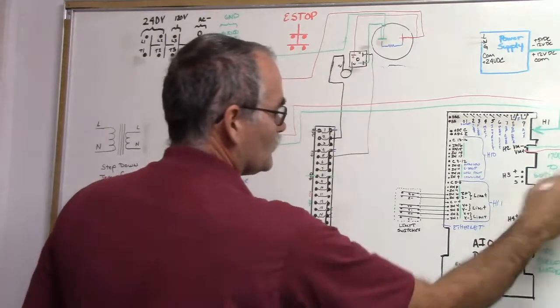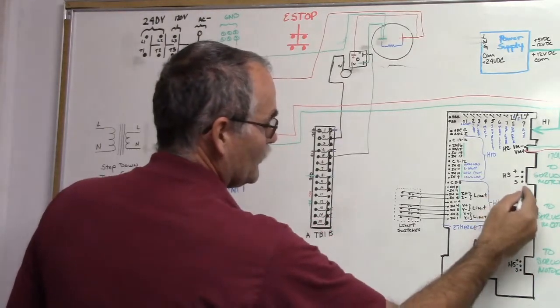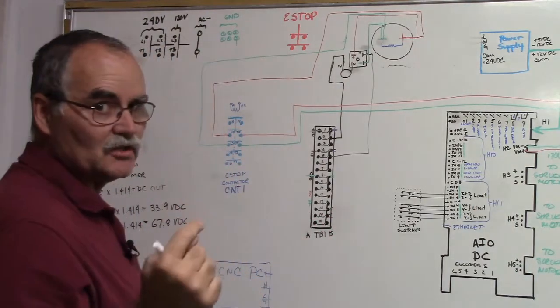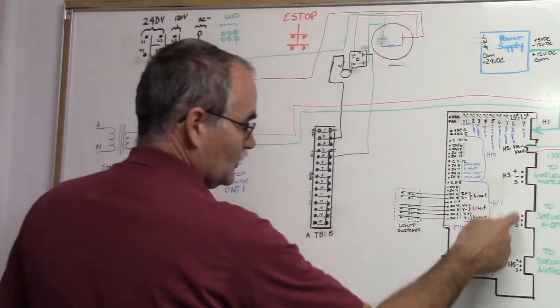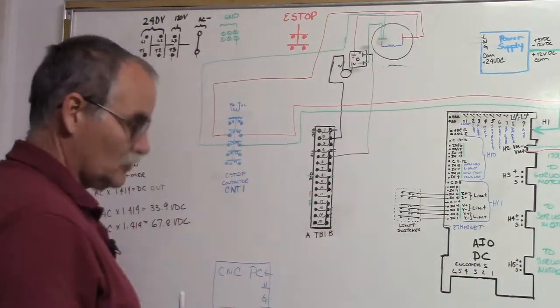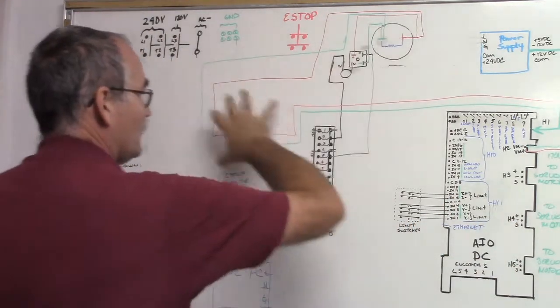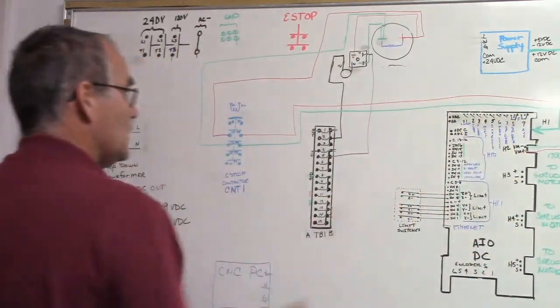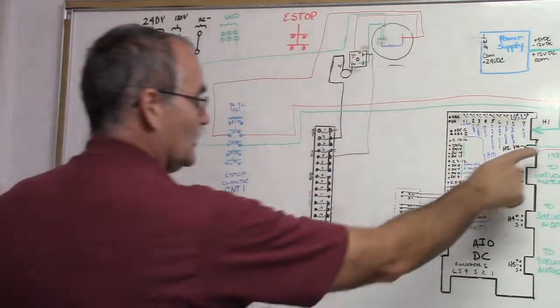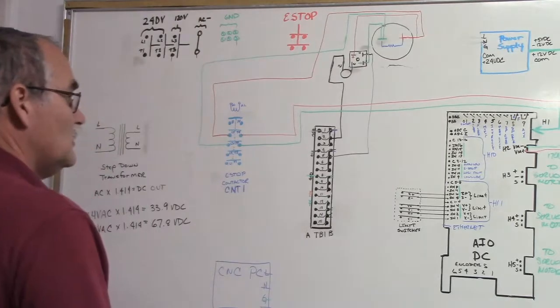This is where you connect your servo motors and they're labeled and there's a shield. Your cable should have a shield, a drain wire that gets landed on these shield terminals. So we've completed a circuit, assuming direct rectification, 170 volts is getting to the all-in-one DC.